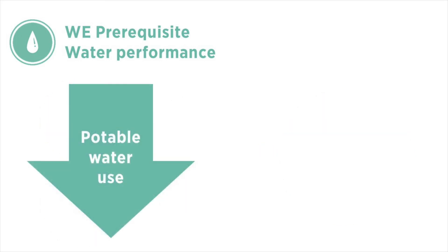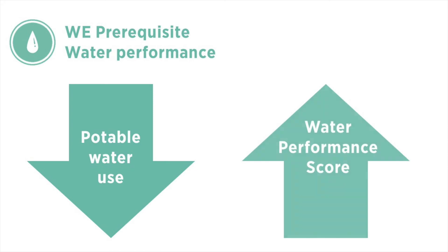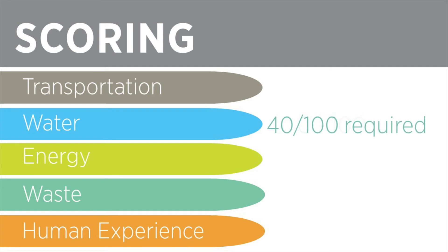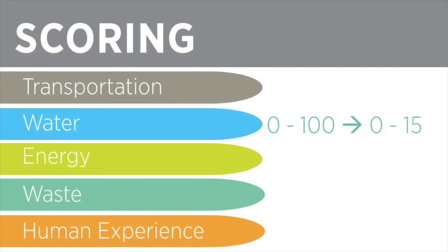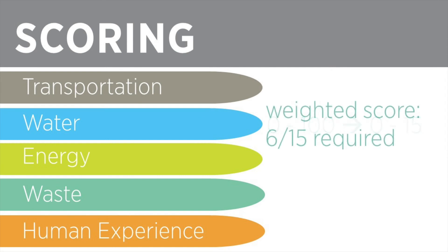As you would expect, lower potable water use results in a higher water performance score. Projects earn a 0 to 100 score to give an easy-to-understand snapshot of how the building is performing. To achieve certification, projects must earn a score of at least 40 out of 100 in each category, including water. These 0 to 100 scores for each category are then weighted to reflect the contribution each category makes to LEED system goals. The 0 to 100 water performance score is weighted out of 15, so the required 40 out of 100 score corresponds to at least 6 points.